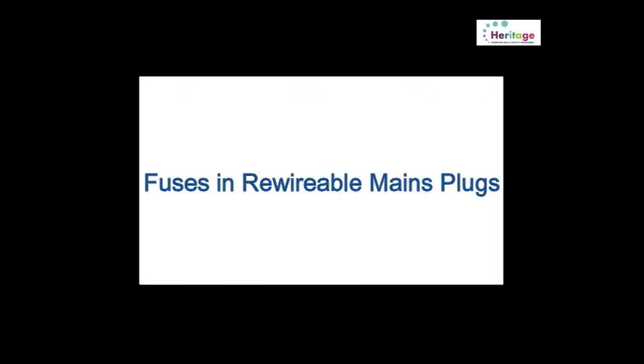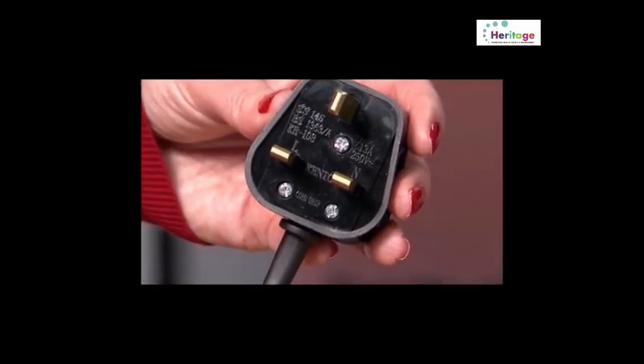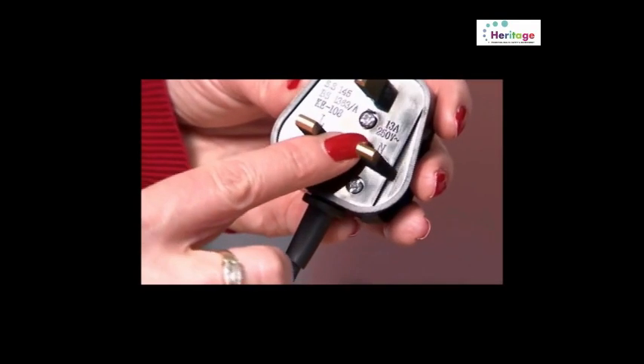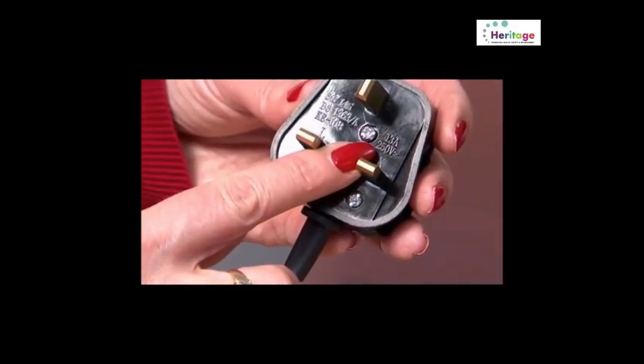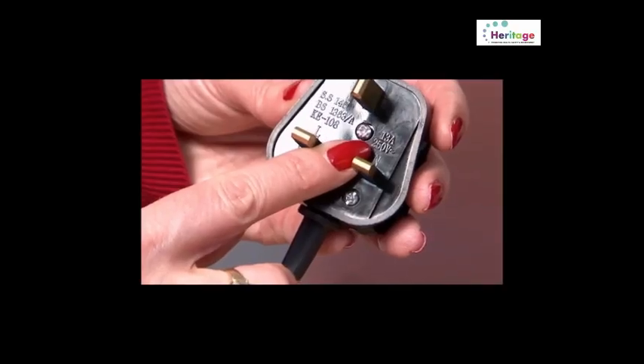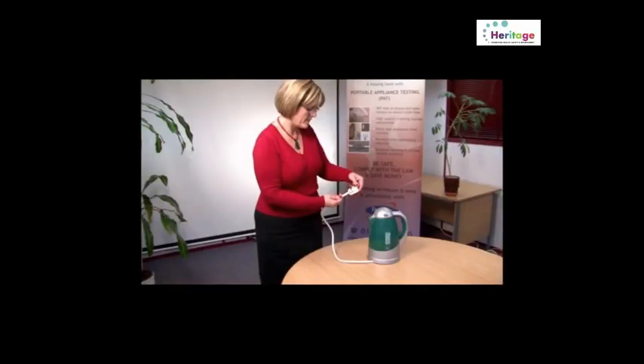Fuses in rewirable mains plugs. These are plugs which the user can wire. Rewirable plugs have 13 amps marked, as they can handle a maximum of 13 amps. Many people assume that this means a 13 amp fuse should be used in this appliance, but this is not the case.